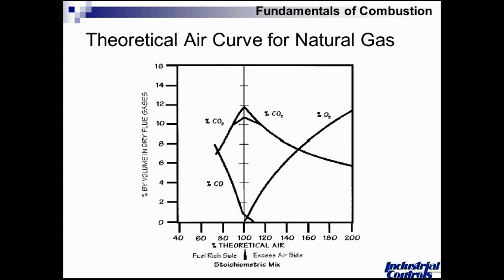On the left-hand side of the 100 percent mark, we're starting to burn rich, meaning we're bringing more free carbon into the equation than we've got free oxygen to oxidize with. So now we begin to generate the carbon monoxide that we really want to avoid. What you'll see along the top is a curve of carbon dioxide, which for many years was one of the measurements we made when setting up burners before we had the ability to quickly measure carbon monoxide.